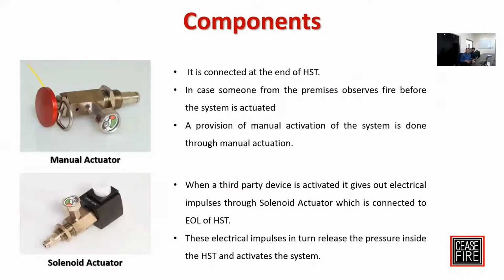These are for the manual actuation, and the solenoid actuator is for if you want to actuate the system with any third party. So tomorrow, if any customer says, I want electrical actuation, I want to actuate the system with smoke or heat detectors, we can also make a provision using these components. Depending on the customer's requirement, we can make it automatic with the electrical, or we have a tube system which can make it 100% mechanical. Our recommendation is to go 100% mechanical. If a customer specifically requires it, we can also give them a dual actuation system.